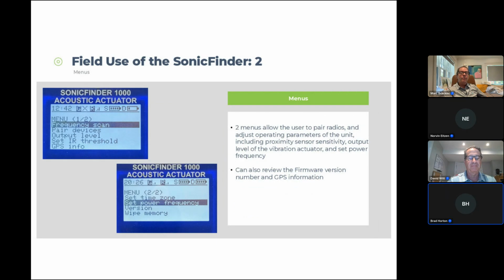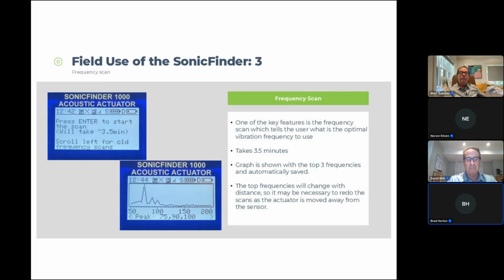The menu is really easy. The one that you're going to use the most often is the very top, which is frequency scan. We do a frequency scan at each location until you learn your territory, and then you kind of know which frequencies work best. But initially, the first thing you're going to do is a frequency scan, and it's going to tell you the top 3 frequencies, as well as give you a graph that displays the results for the entire frequency spectrum that we use, from 50 to 200 hertz. And then it's simple just to back out of it, set your frequency, and go right on. Next slide, Mark.